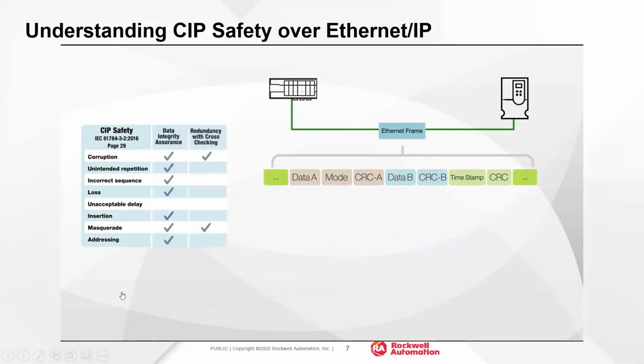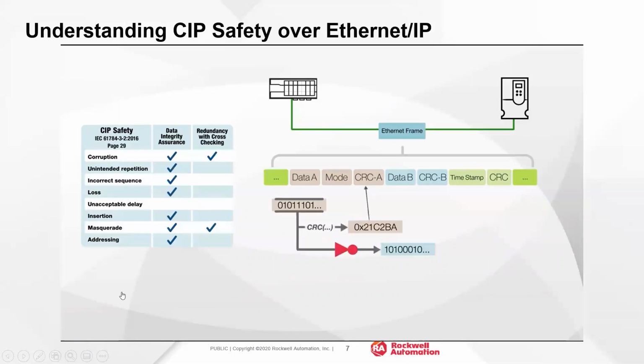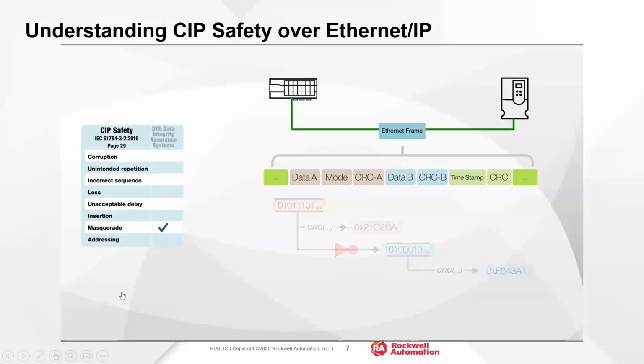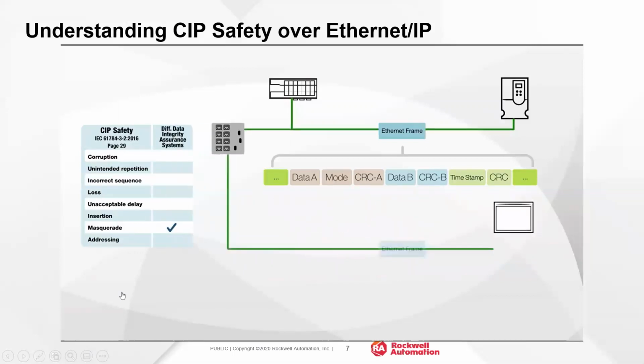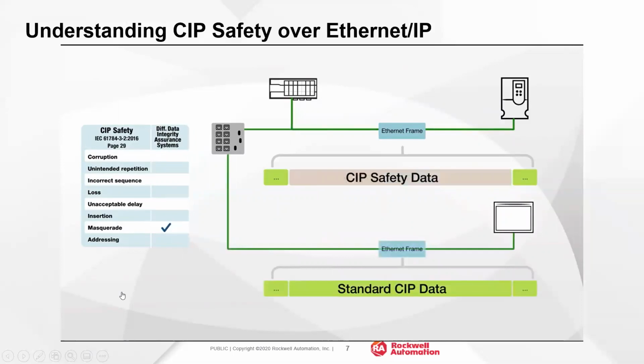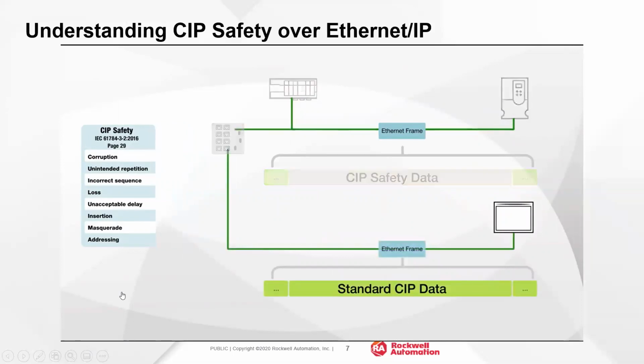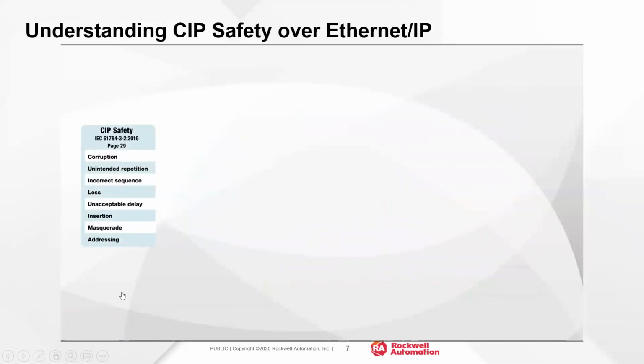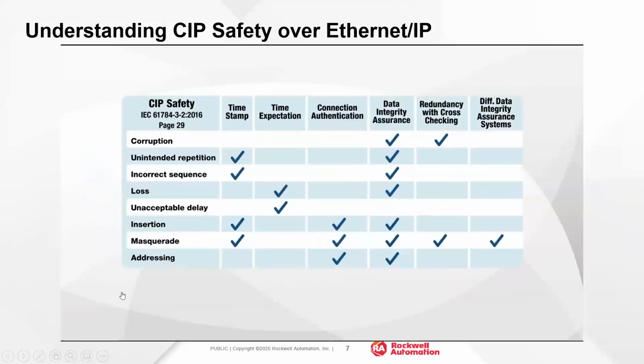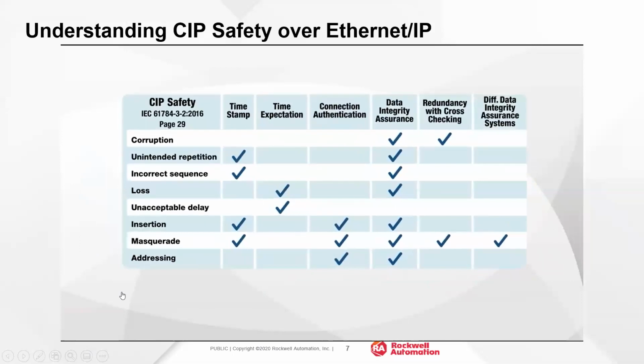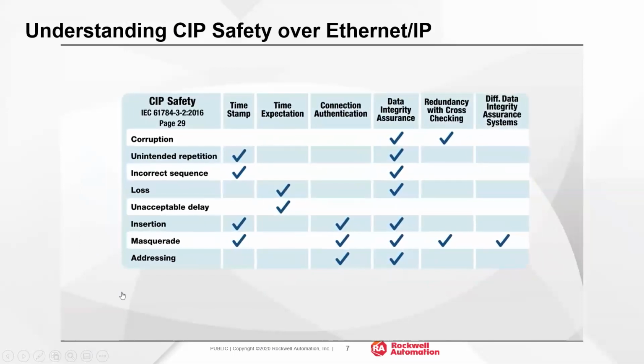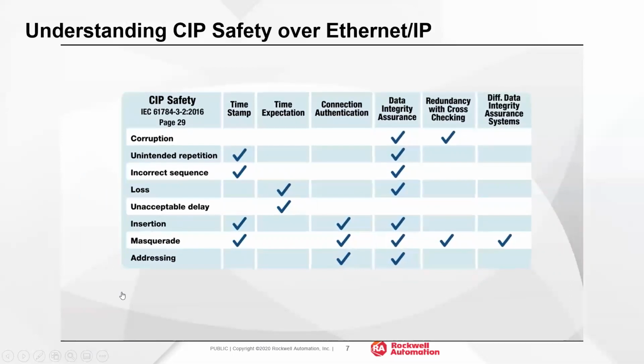There is a 16-bit CRC appended to the data, plus an inverted version of the original data and a 24-bit CRC of the inverted data and timestamp, split into two parts. This prevents accidental corruption of bits from being undetected. The previously mentioned methods are only used by safety devices to prevent standard data from being interpreted as safety data. All of these together, plus additional measures for configuration, allow a single Ethernet cable to deliver fault-tolerant functional safety.